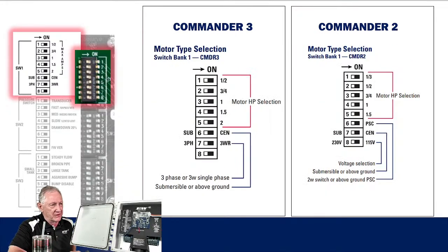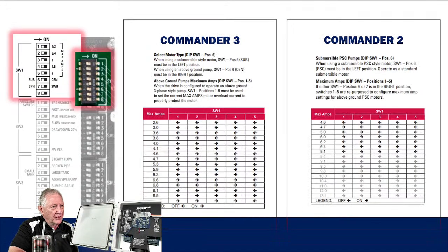If this is going to be a centrifugal motor, when you look at the top bank up there again, let's see if I've got a bigger slide of that. Whoops, I don't. With centrifugal motors, in lieu of setting a horsepower, as we do with submersible motors, we're going to set it up based on what we call max amps. This chart, by the way, is in the instruction manual. You've got max amps listed over on the left-hand side, and across the top are your dip switches.